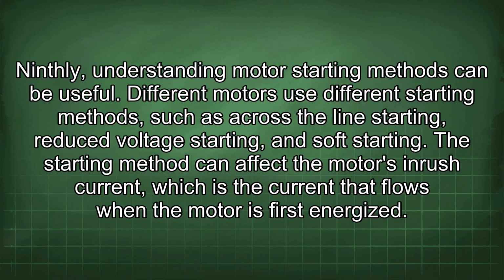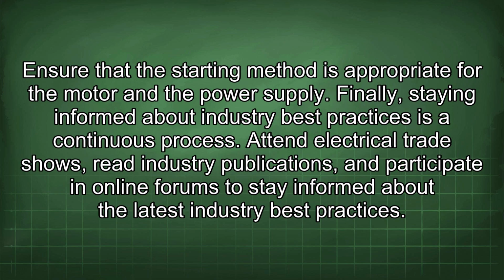Ninthly, understanding motor starting methods can be useful. Different motors use different starting methods, such as across-the-line starting, reduced voltage starting, and soft starting. The starting method can affect the motor's inrush current, which is the current that flows when the motor is first energized. Ensure that the starting method is appropriate for the motor and the power supply.